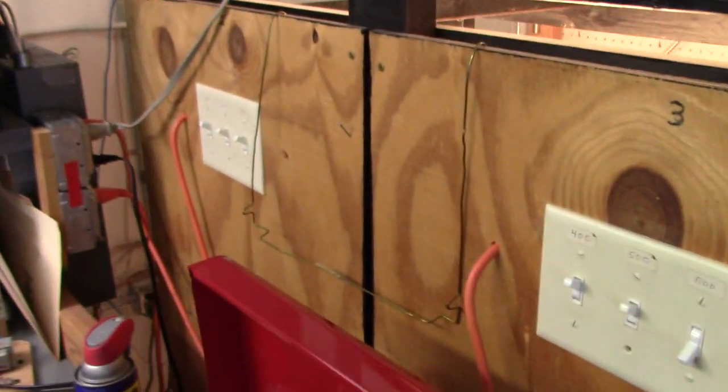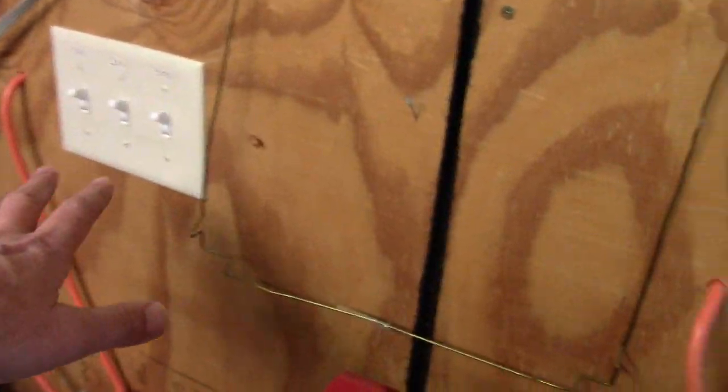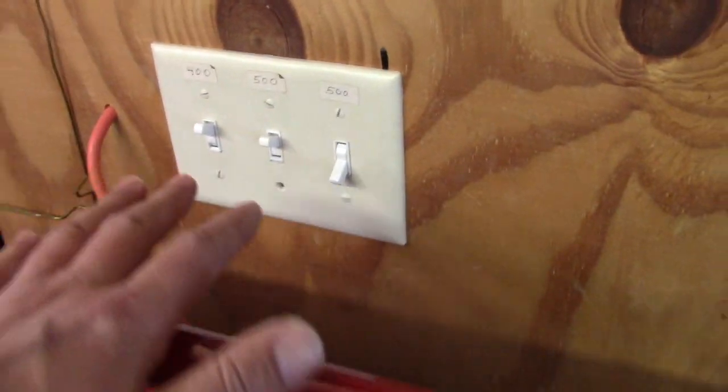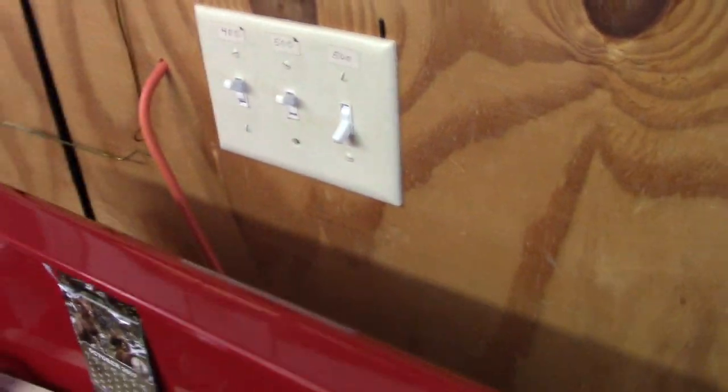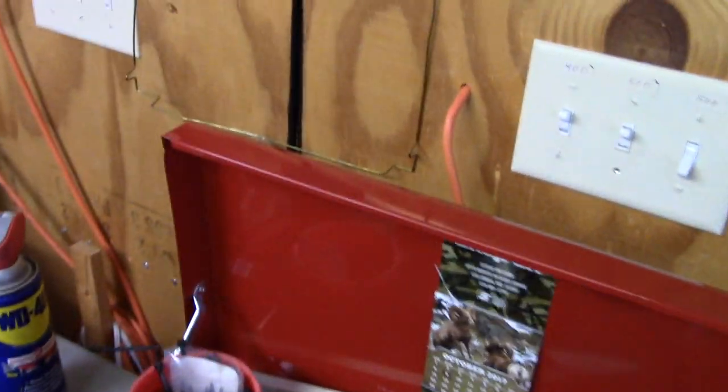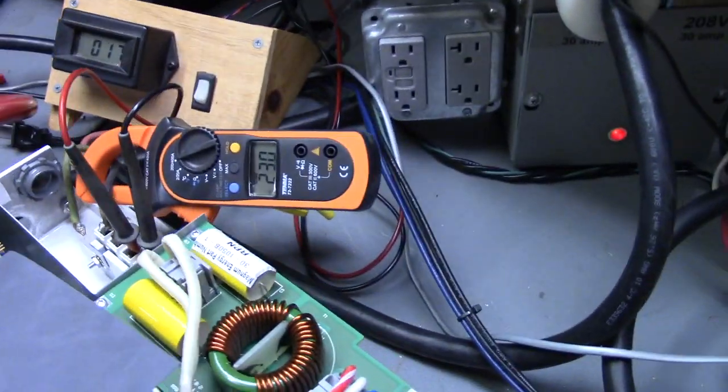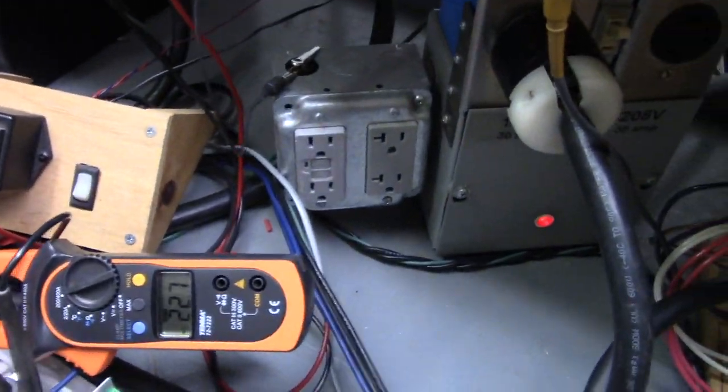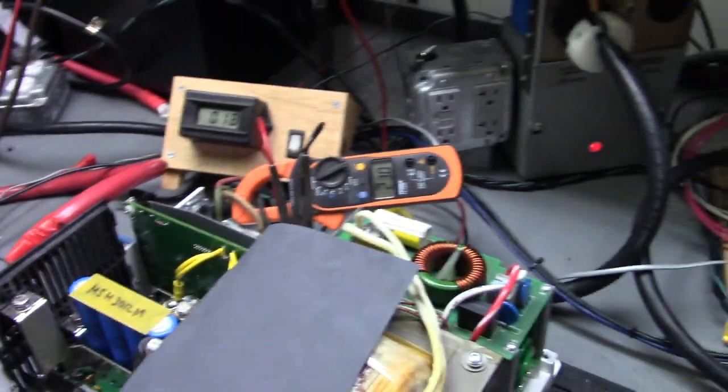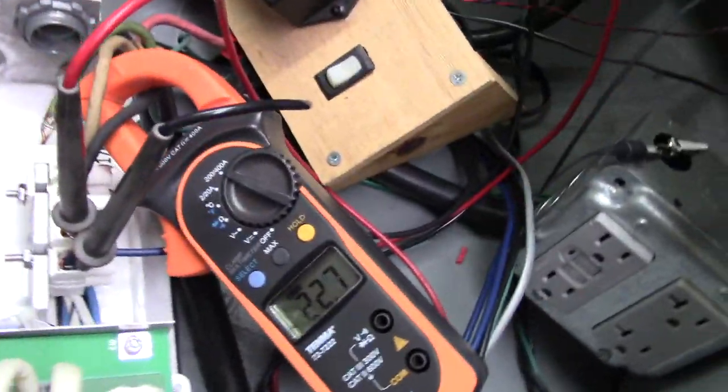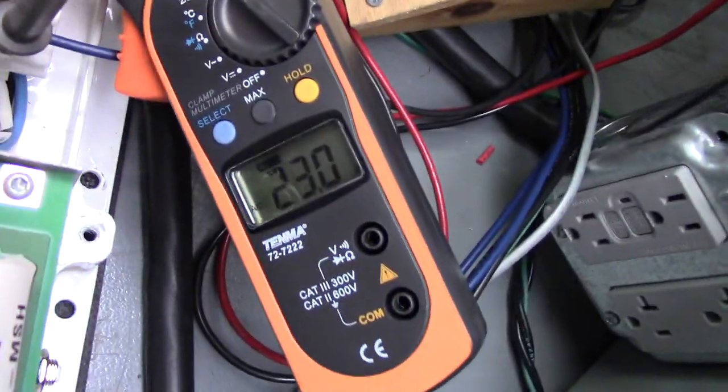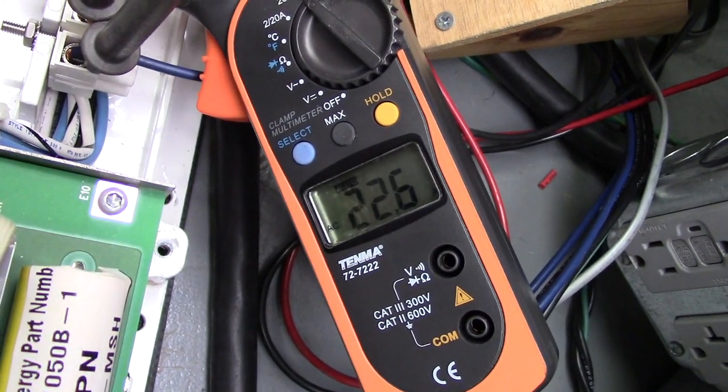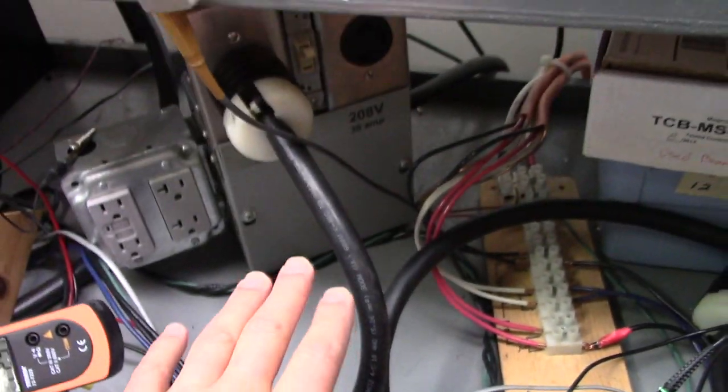And the actual current coming in right now. I have my load box. Let's see, each of these is 500, it's 1500. So I've got 2500 watts of light bulbs running in my load box. So I've got 2500 watts load on this. So the combined current for this 2500 watt load and the battery charger right now is pulling 22, 23 amps off of my shore power.